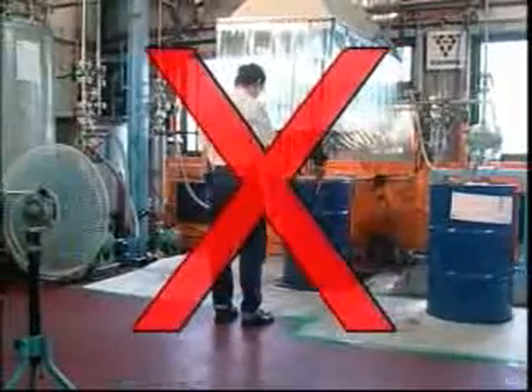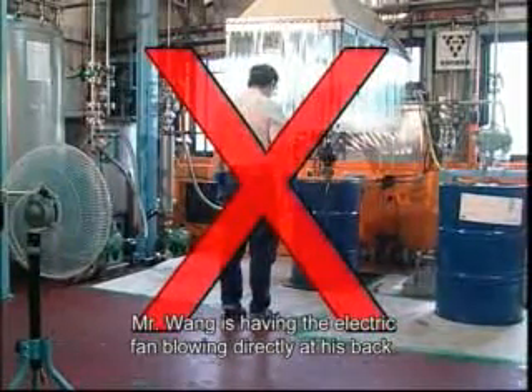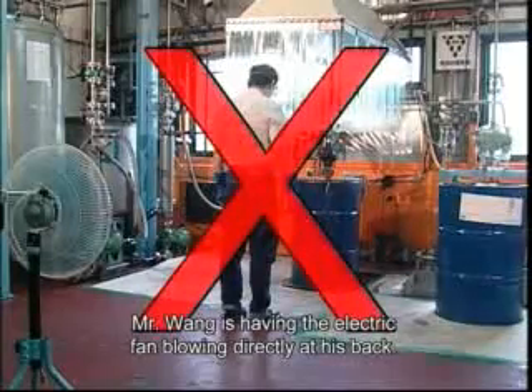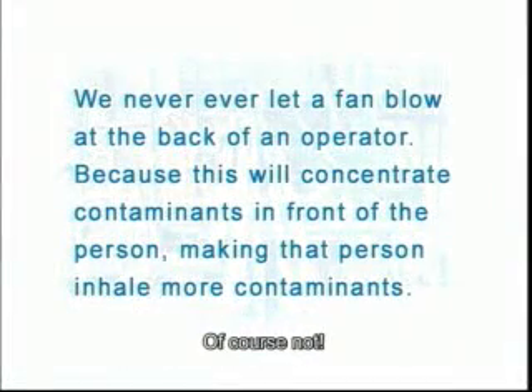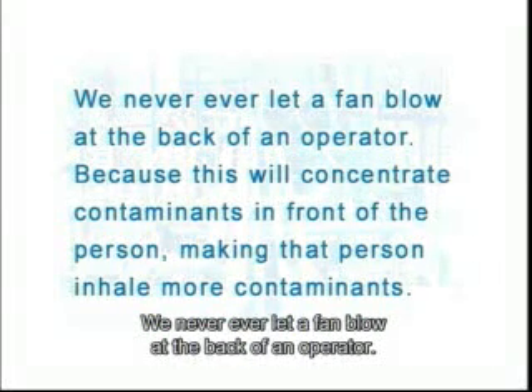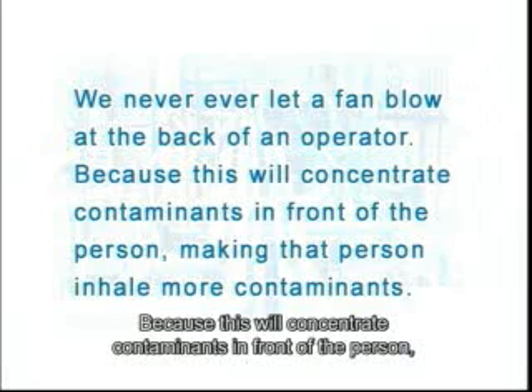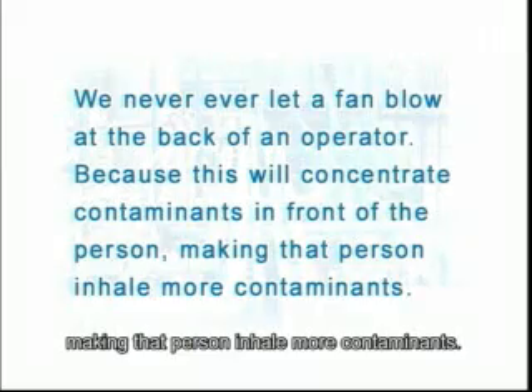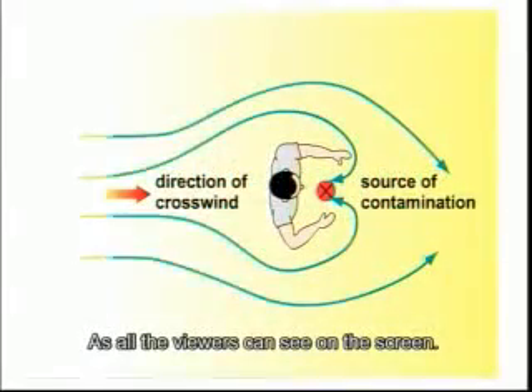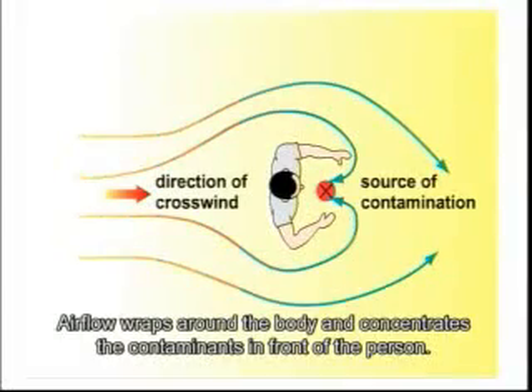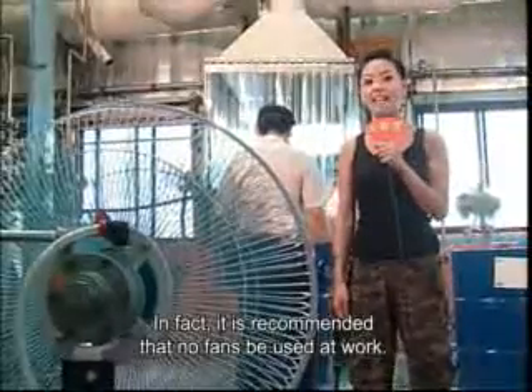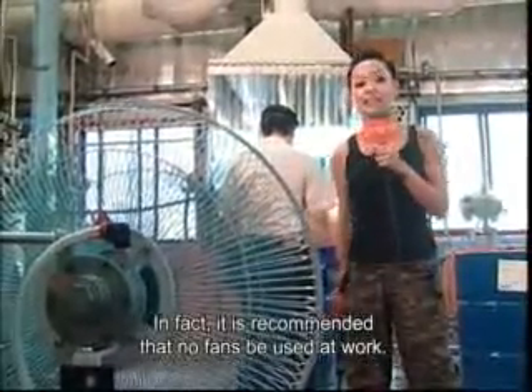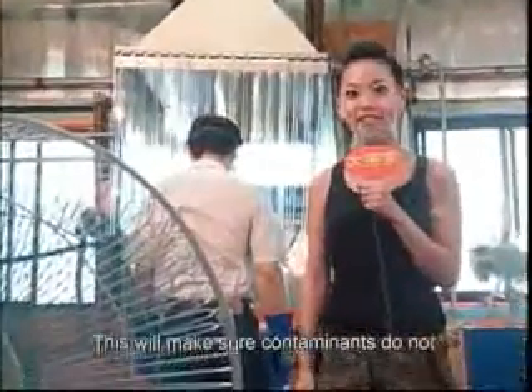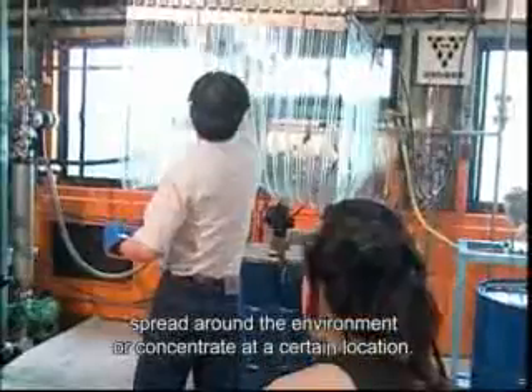Mr. Wang is having the electric fan blowing directly at his back. Is it correct? Of course not. We never ever let a fan blow at the back of an operator, because this will concentrate contaminants in front of the person, making that person inhale more contaminants. As all the viewers can see on the screen, airflow wraps around the body and concentrates the contaminants in front of the person. In fact, it is recommended that no fans be used at work. This will make sure contaminants do not spread around the environment or concentrate at a certain location.